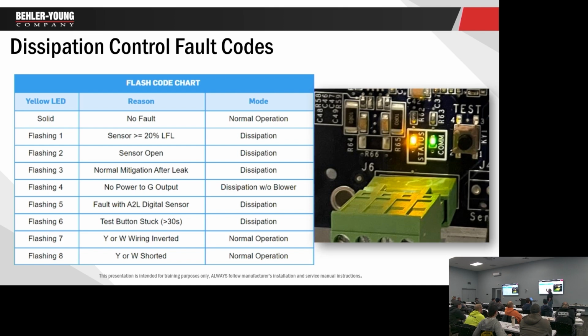Normal mitigation after leak, no power to G terminal, fault on sensor, test button stuck, wirings are inverted, or there's a short. The codes will clear, so what'll happen, it'll go to mitigation if it senses that. And after the refrigerant's cleared, it'll mitigate for 15 minutes, and then it'll go back into normal operation. The code will clear, but you can use that button to recall the code. So if you go back there and say, this thing's not working, it's out of refrigerant, and you look, well, it's mitigated 3 times. Okay, that explains it.